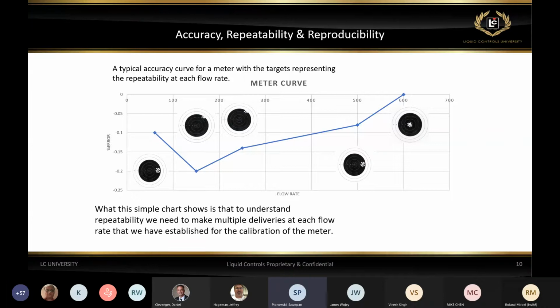That's a fairly good meter that meets most of the requirements, most of the standards across the world, being either, again, US, Canadian, or NIST standards. So it's a really good meter. And again, the key here is testing at different flow rates, calibrating it at high flow, testing at different flow rates, and really doing repeatability testing at each flow. When you go through that kind of process, you know how good this meter is.